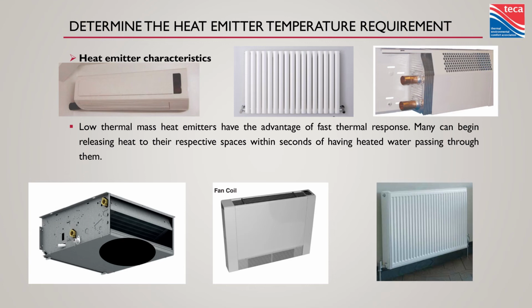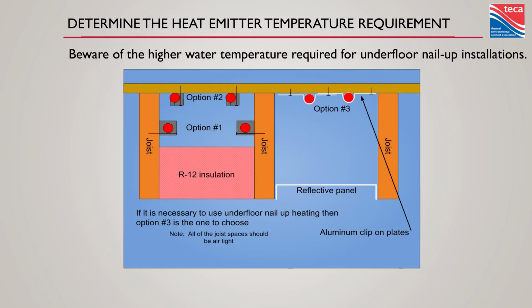Something that has some help for heat transfer. A pipe with some aluminum or steel being used to wick heat away from that tube, transfer heat around a bigger space, get lots of surface area between what's coming through that pipe and the subfloor. Because remember, we're trying to heat what's above this floor, not down here. So heat transfer plates come from all kinds of different places. Great way to lower your leaving water temperature on a system like this.